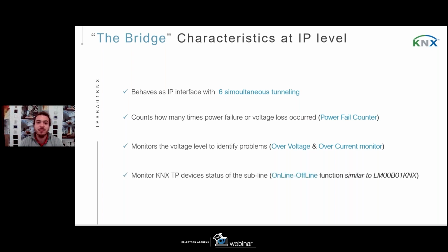And in addition, we have the opportunity to enable the online-offline function on this device. That is similar to our logic module LM00B01 KNX that we saw in a previous webinar, where we can say how many devices we have in our KNX trunk and check if they are online. If the bridge doesn't receive any command for a while, it starts to perform some memory reads on these devices to understand if they are online or not. If not, an alarm telegram can be sent to the KNX bus to advise, for example, a BMS system that a particular device is not online at this moment.